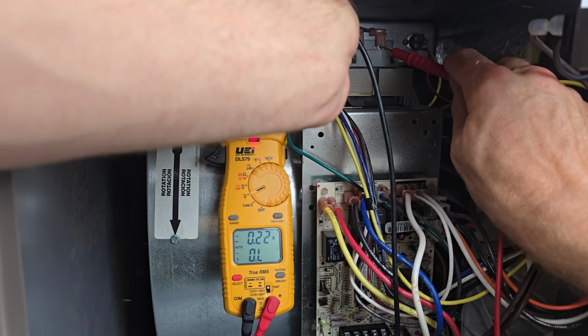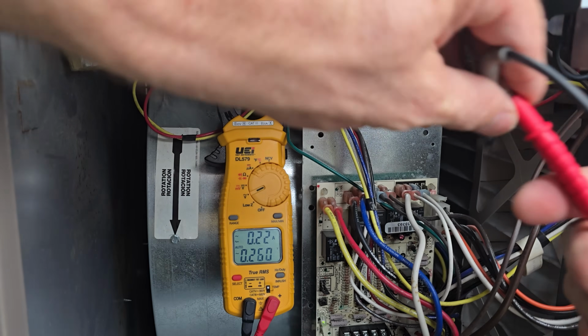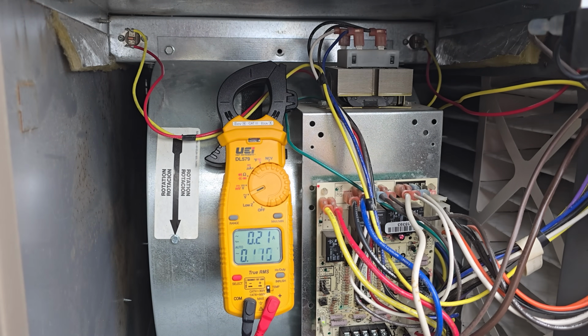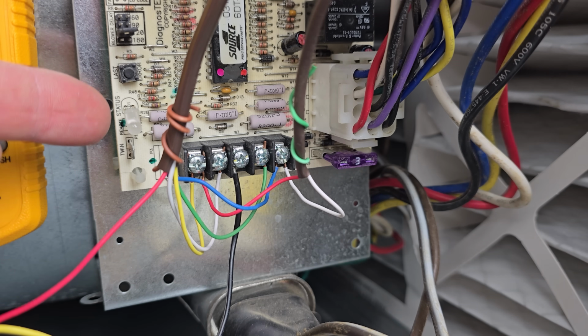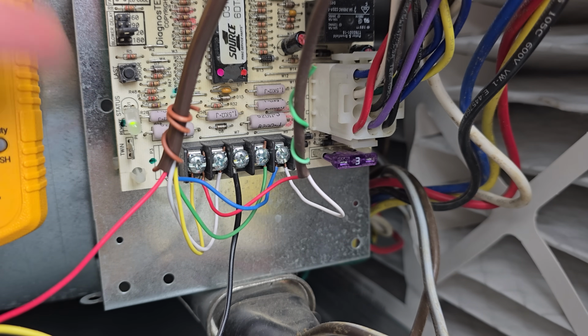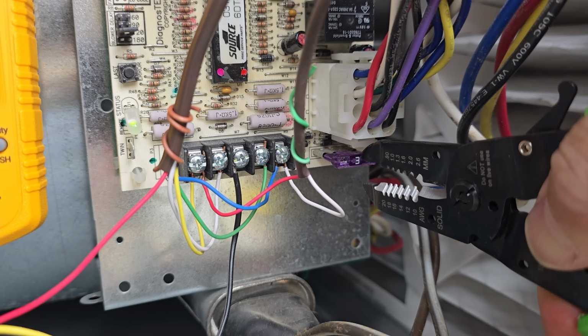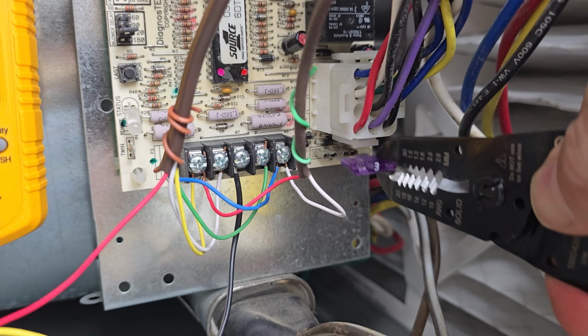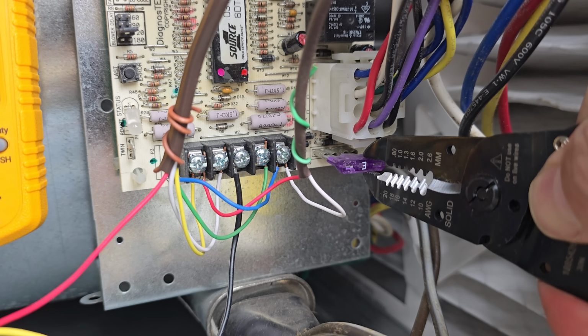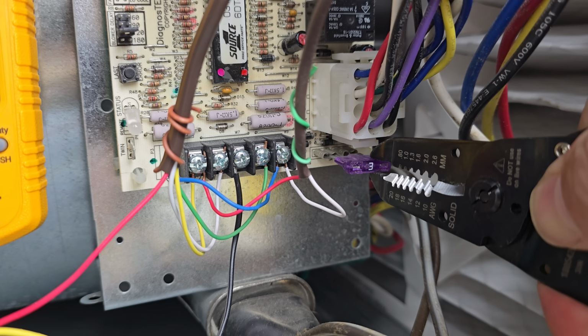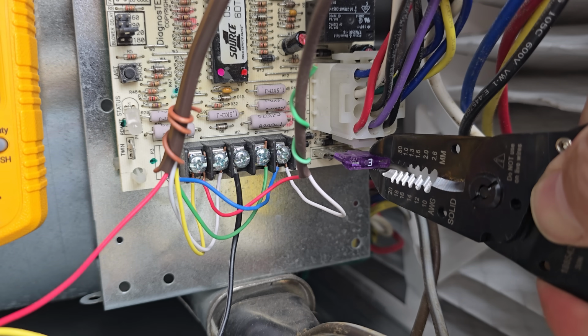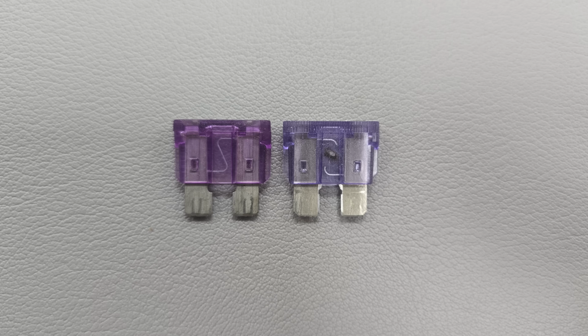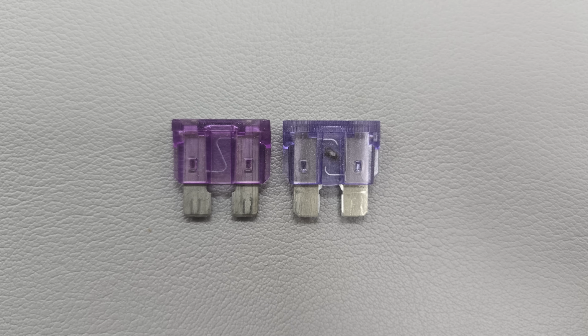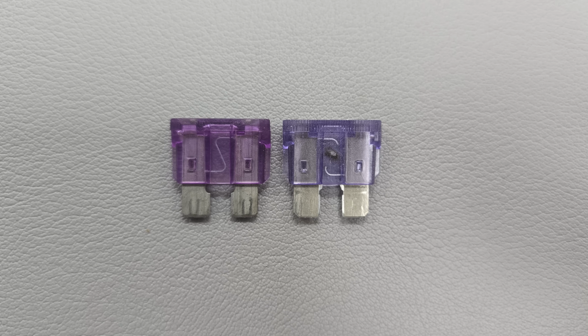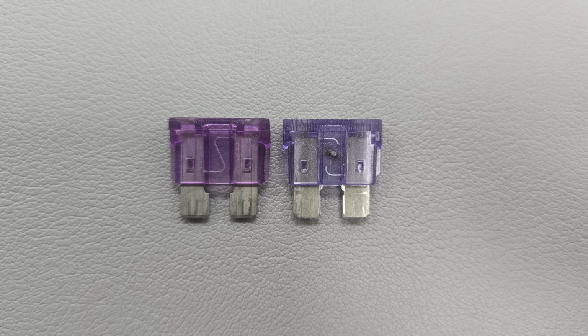Now, if you still have 28 volts here and your status code light is not lit still, then you could have a bad 24 volt fuse. So once again, in this case, you can see that the LED status code light is flashing, and it's flashing slowly, indicating normal operation. And so the thing is, if it was not, it may be due to a bad 24 volt fuse. So you see the LED status code light is now not lit. Now, not all furnaces will have this occur. Some will show a status code error that says that the 3 amp fuse is blown. Hopefully you can see this, but the one on the left is good. The one on the right is bad. That's blown. It has that popped section in it. And so that could be the issue.